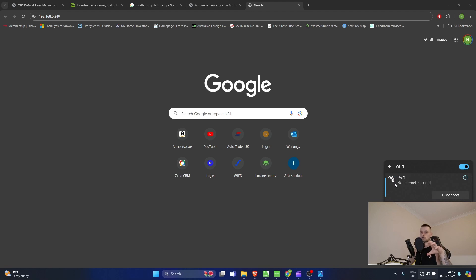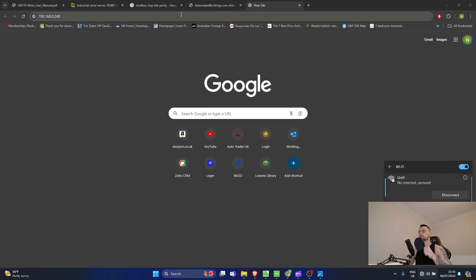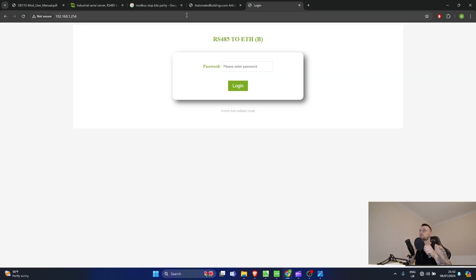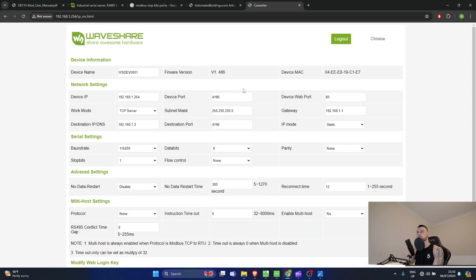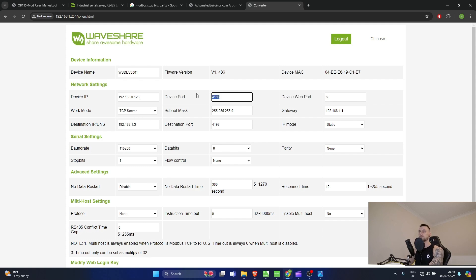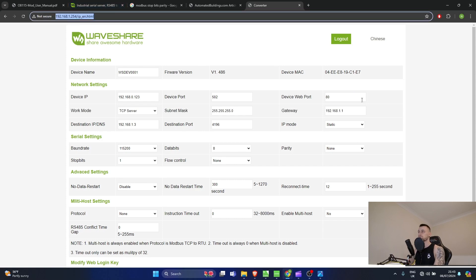I can now go to the default IP address and immediately reach the RS485 to Ethernet gateway. I log in - there's no password by default, so I just press Login. In the configuration page, first I set the device IP. I'm currently on 192.168.1.254, but I want to move it to 192.168.0.123. I'll also change the device port to 502, which is where I'll be sending and receiving information. The web port I'll leave on 80.